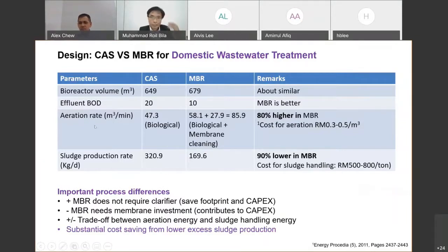Okay, aeration rate, aeration energy, you see here MBR is 80% higher. Why do we need such high aeration? Remember that the sludge concentration is high. When you have a high sludge concentration, it means that you have more microbes. They can consume more food, but they also need more oxygen. So that is one of the reasons. The second reason is that if I have a membrane, I need the air to scour off the foulants. So MBR will consume 80% higher energy, but the thing is the cost for aeration is not much.